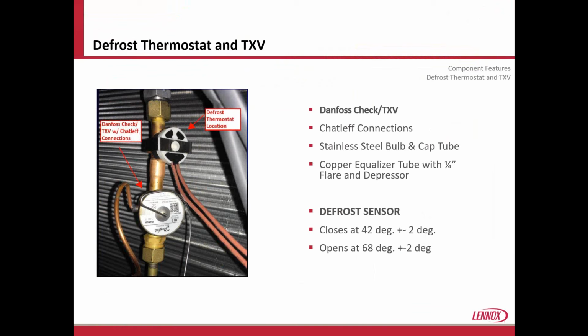On our time and temperature type of control, this is on a split ML14 unit here, condenser, which I think you guys have some of these in stock. The defrost sensor is going to be located right at the expansion valve. Okay, this sensor is going to open or close at 42 degrees plus or minus 2 degrees. So anything below 42 degrees outside, whether there's frost in the air, whether there's moisture in the air or not, it will actually close and can go into defrost for a few minutes. It opens at 68 degrees.